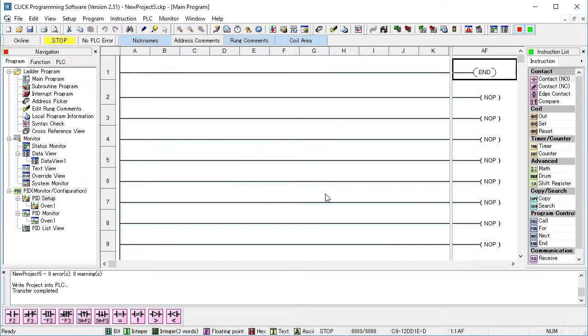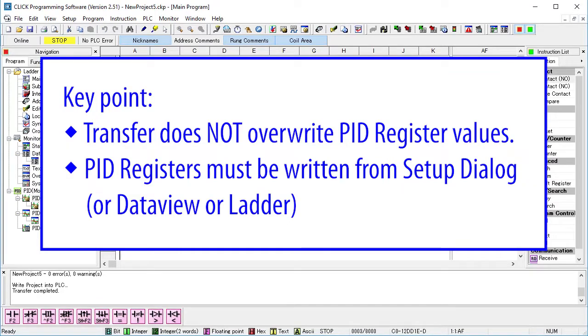but it did not write the PID register values because you may not want to overwrite an existing PID configuration setting when transferring a project, right? Which explains why we were able to write the registers from the PID setup dialog before we transfer the project. They are completely independent.